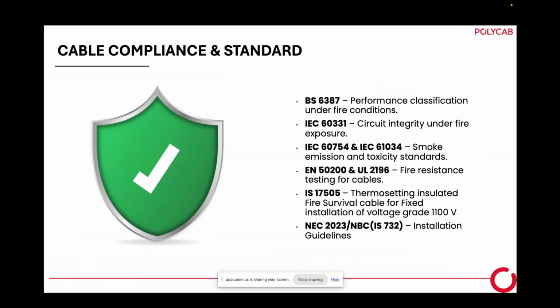So compliance. Now many manufacturers are manufacturing fire survival cable. How do you know whether a fire survival cable is reliable or not? Normally there are standards. As I told you, BS 6387 is the highly popular standard. If we follow this, the cable is safe. Performance of the cable as per 6387 is quite famous, and it gives good measurement and good values. Another is IEC 60331, a circuit integrity test at 750-degree temperature. 6387 overtakes 60331. 60331 is a very old circuit integrity test specification.